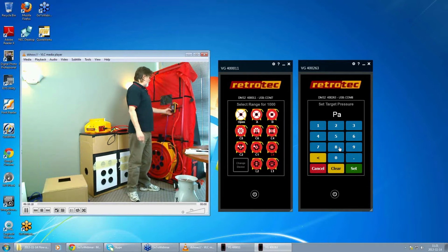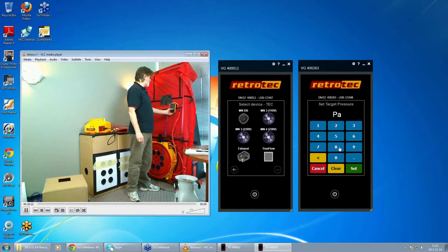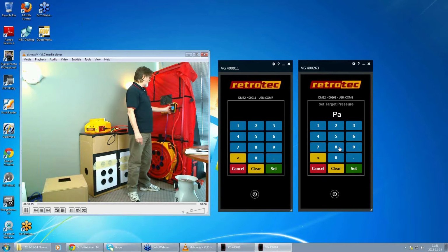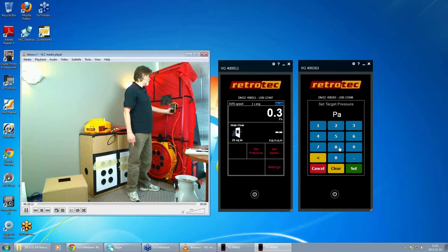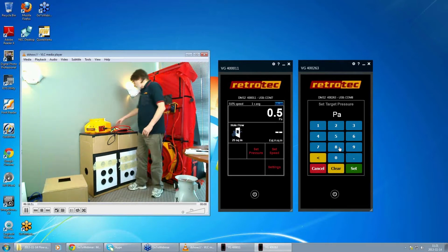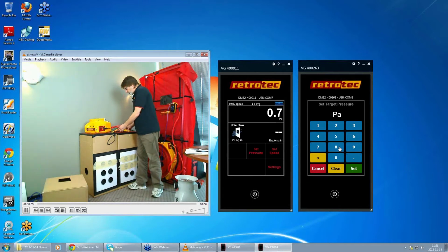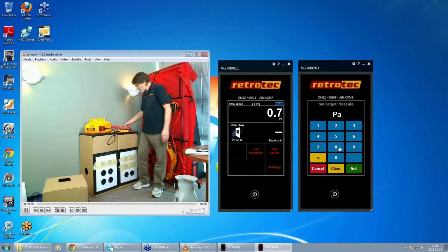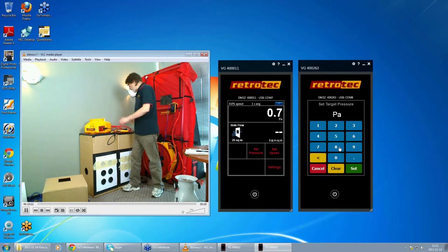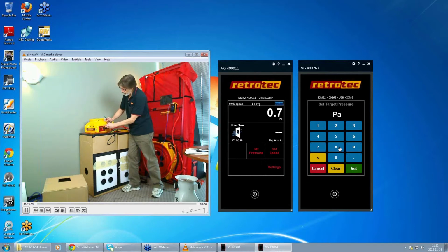And over here we're going to go to what we call hole flow. Change device, hole flow, 25 square inches, which is what that is. If it's different than that, you can enter it in here. Set that. So we're all set up for hole flow. We had this set up to EQLA, which is a way of representing hole flow. We can also represent it as CFM if we want. So we've got that set. On this side over here, we're going to hook up our duct tester, so we need some power. These are the flow connectors. Hook those up. Notice we're in the depressurization direction.